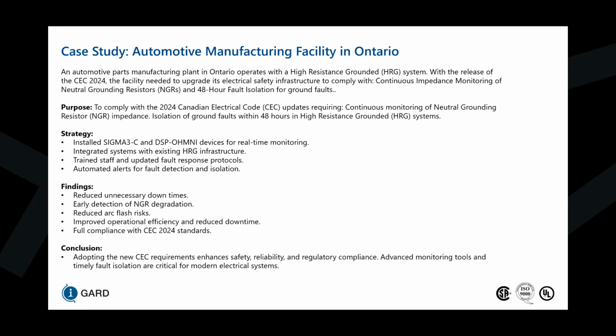In addition to that, that 48-hour delay gave them a bit of time before they had to shut down the system. So back when resistor monitoring was introduced in the 2018 Canadian Electrical Code, you had to trip the system basically right away on resistor fault. So with the new code requirement, we're seeing that they're allowing for a 48-hour delay.